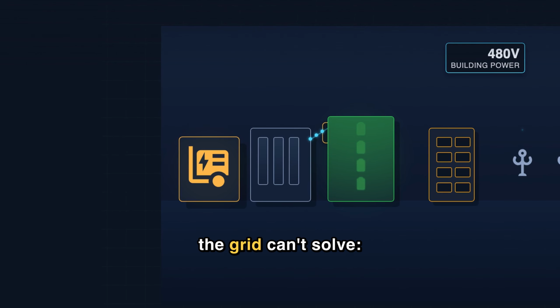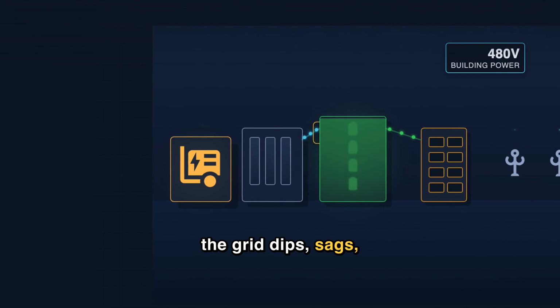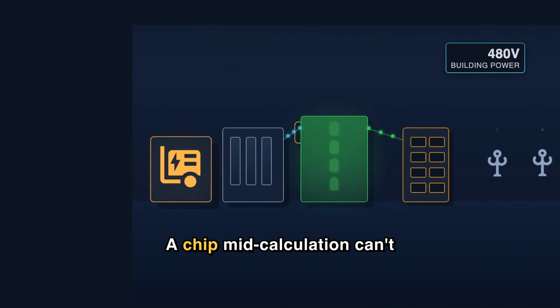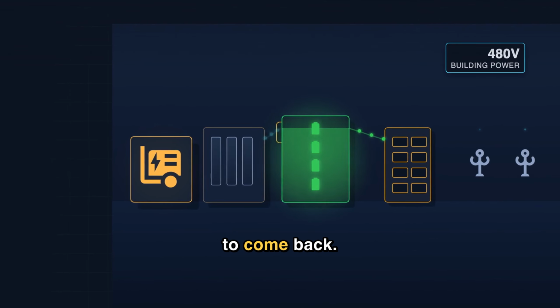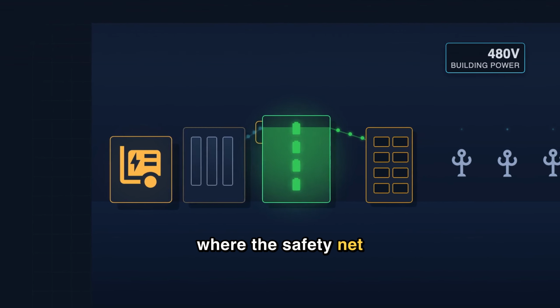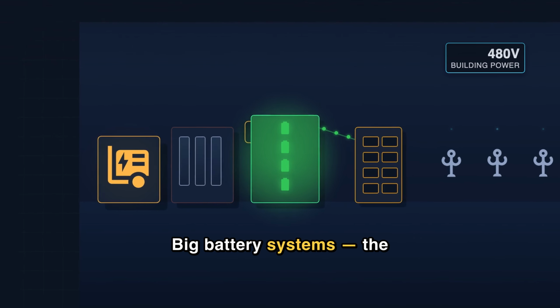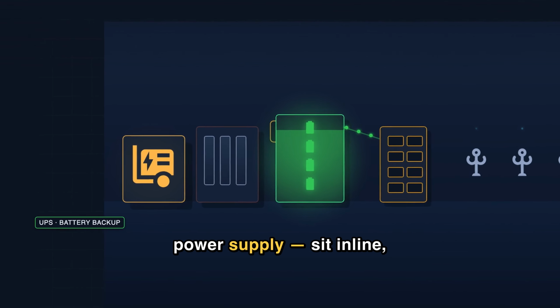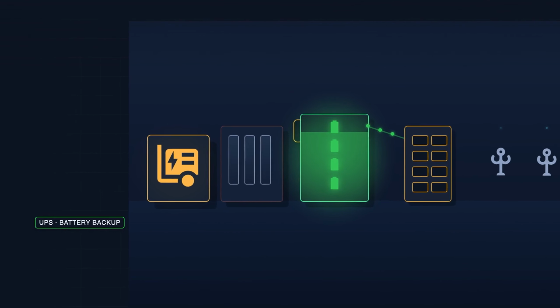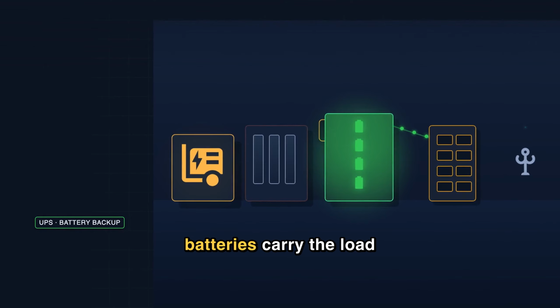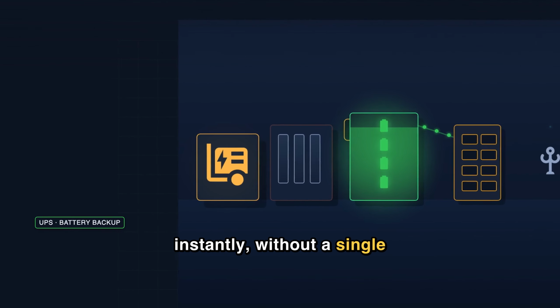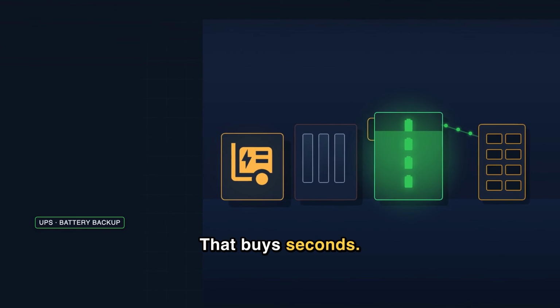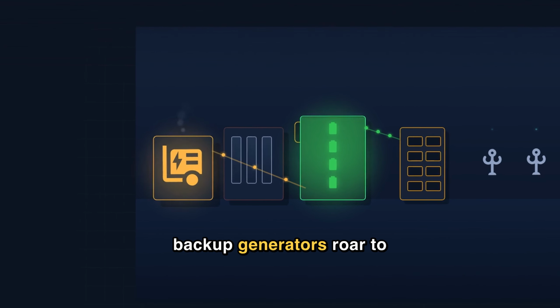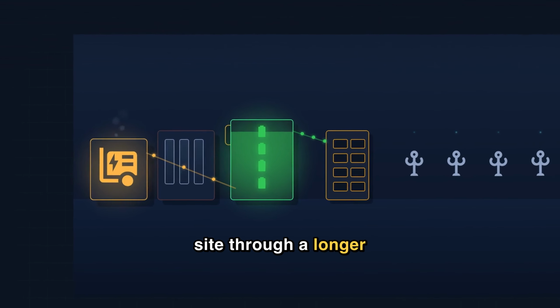But here's a problem the grid can't solve. The grid dips, sags, and sometimes fails outright. A chip mid-calculation can't wait for the lights to come back. So this floor is where the safety net lives. Big battery systems, the UPS, or uninterruptible power supply, sit inline holding a charge. If the grid so much as flickers, the batteries carry the load instantly, without a single missed beat. That buys seconds. And in those seconds, backup generators roar to life to carry the site through a longer outage.